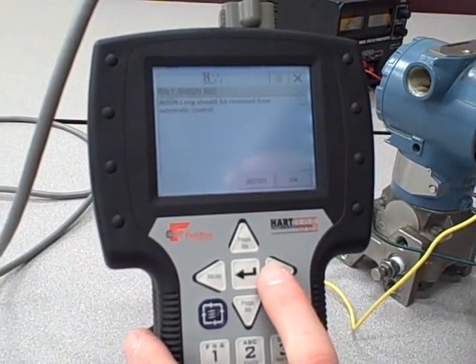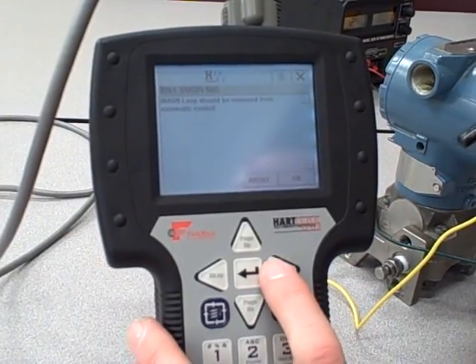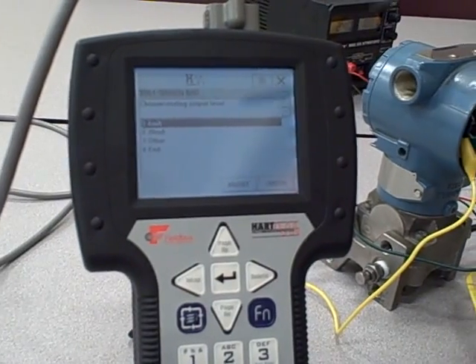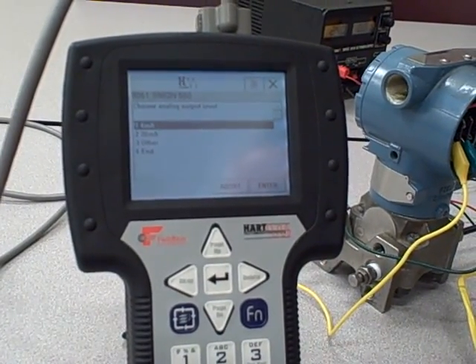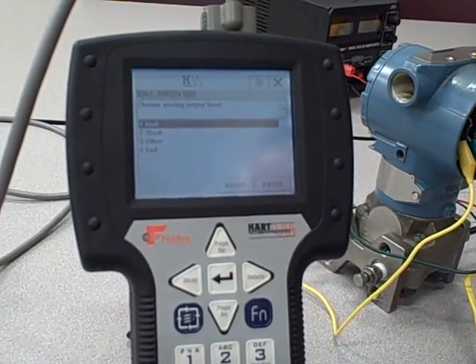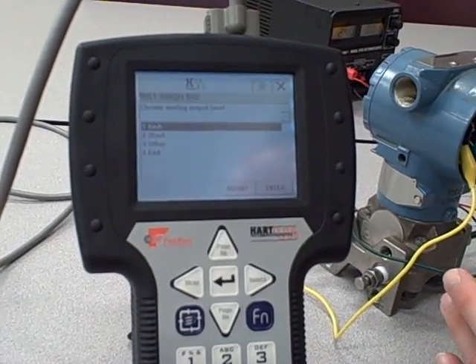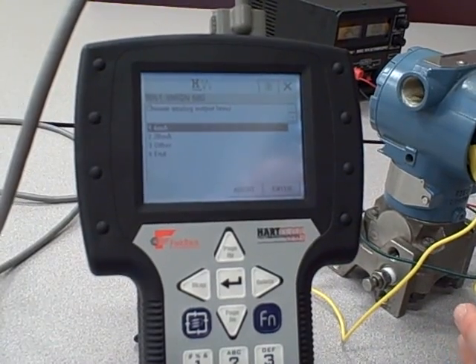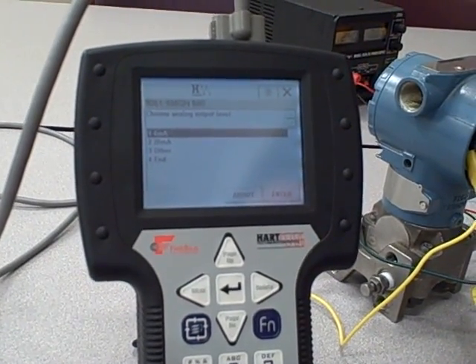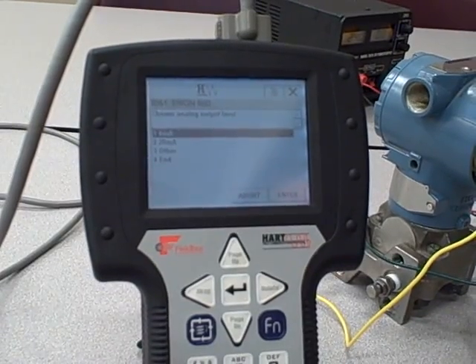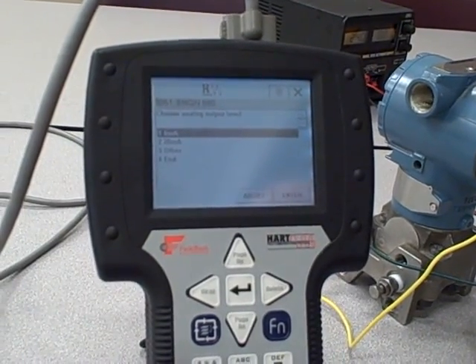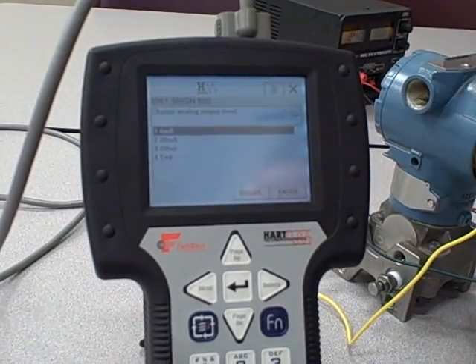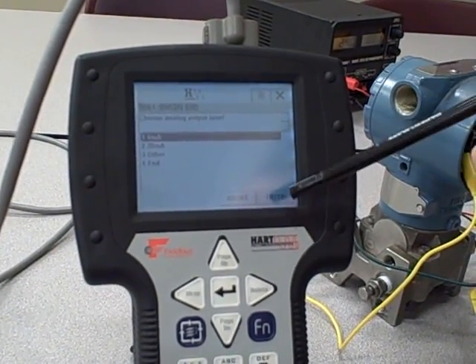It gives you the obligatory warning - the loop should be removed from automatic control. Choose the analog output level. What the loop test feature allows us to do is force the analog current output signal to whatever value we wish, so it will ignore the applied pressure. This is great for checking out loops that are having problems. You can tell the transmitter to go directly to either 4 milliamps exactly, 20 milliamps exactly, or some other value.